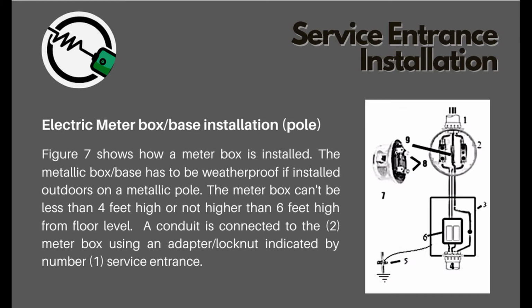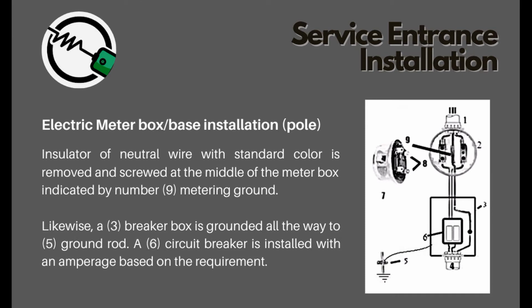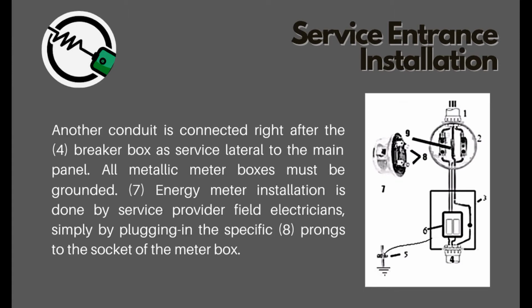A conduit is connected to the 2 meter box using an adapter, lock nut indicated by number 1, service entrance. Insulator of neutral wire with standard color is removed and screwed at the middle of the meter box, indicated by number 9, metering ground. Likewise, a 3 breaker box is grounded all the way to 5 ground rod. A 6 circuit breaker is installed with an amperage based on the requirement. Another conduit is connected right after the 4 breaker box as service lateral to the main panel. All metallic meter boxes must be grounded. 7. Energy meter installation is done by service provider field electricians, simply by plugging in the specific 8 prongs to the socket of the meter box.